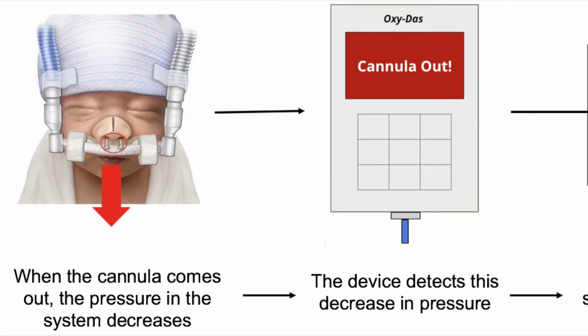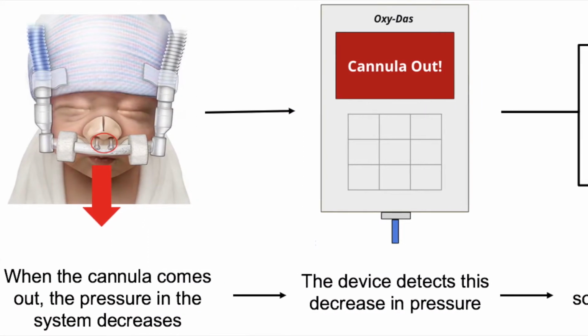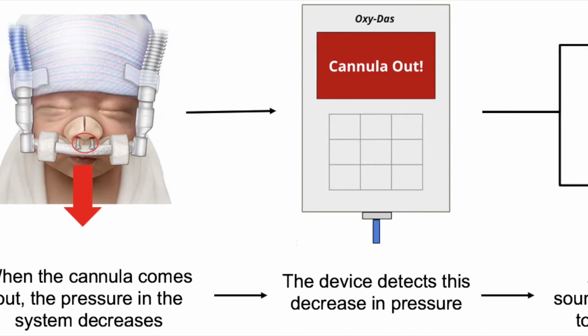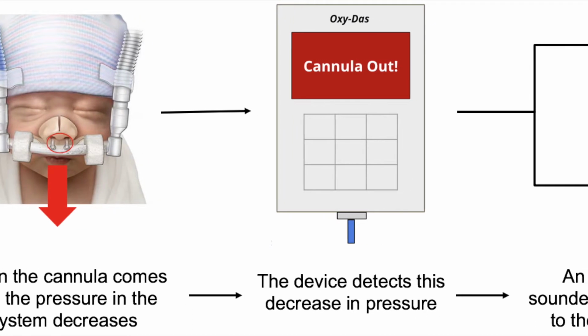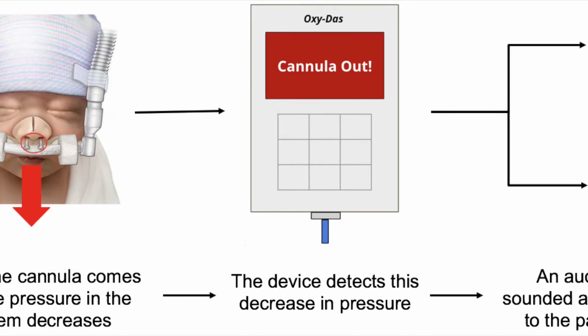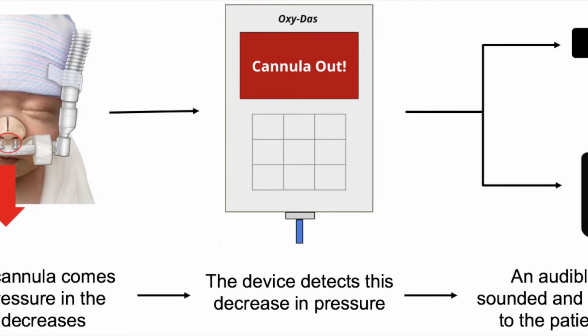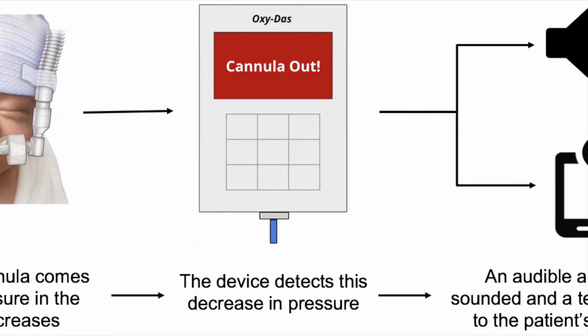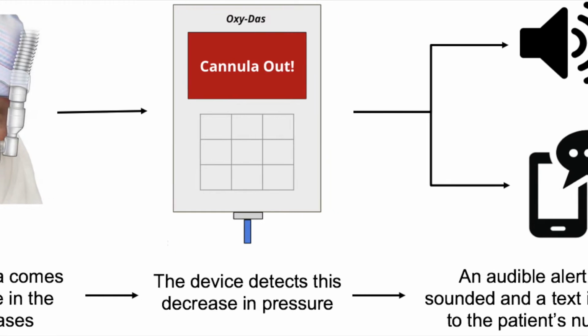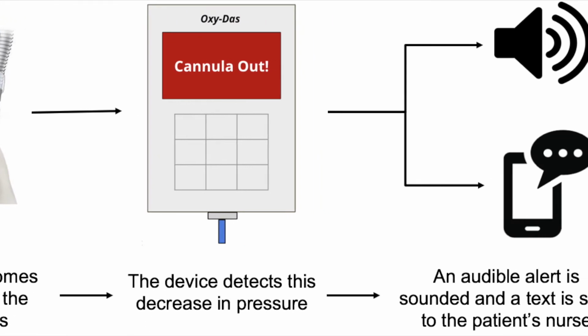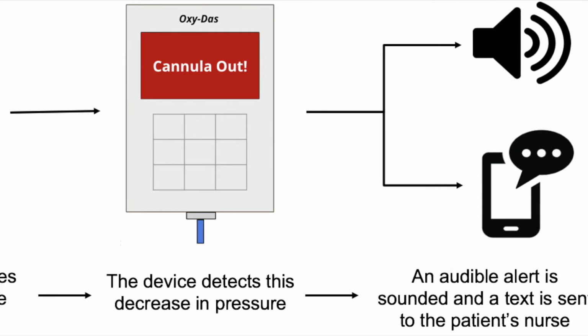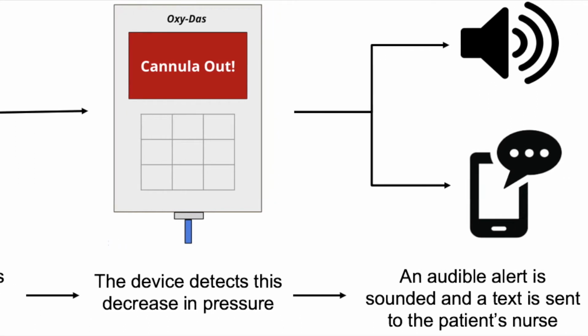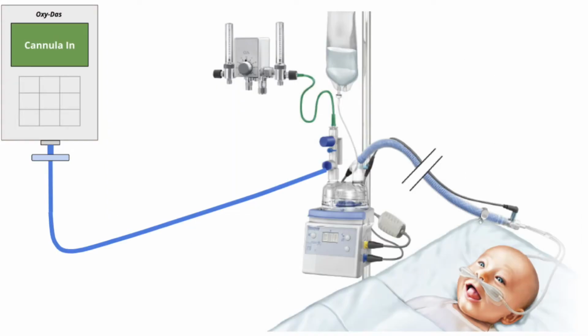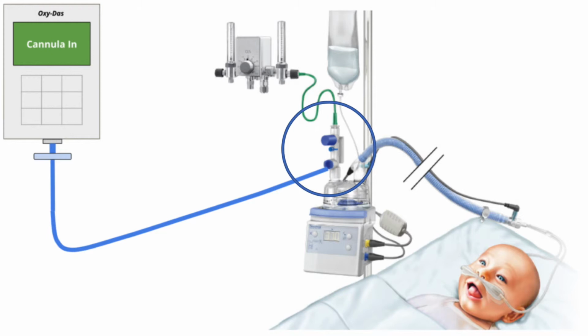Our solution to this problem is a detection and alert system that will notify the nurses immediately when the nasal cannula prongs are dislodged from the nostrils. The device determines whether the prongs are inside or outside the nostrils by measuring the pressure in the bubble CPAP circuit. When the device determines that the prongs are outside the nostrils, it will alert the nurses using an audible alarm and text message system. The device connects directly to pre-existing bubble CPAP machines, making it an easy addition to any NICU.